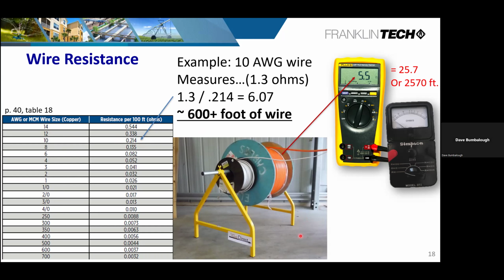Because I've seen it before where contractors have cut so much wire off, put a sticky note on there or write on it. Now, granted, some wire manufacturers actually print the distance of wire on there. But if you've taken it off, put it back on, and maybe it's gotten smudged or some other issue, you're unable to read it. This is a quick and easy way to determine how much is on there.